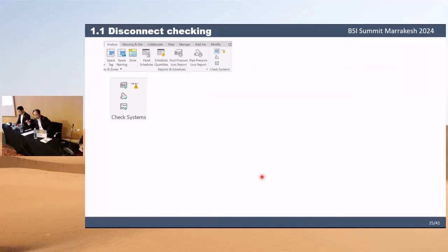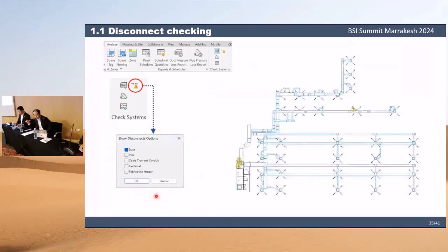On the analysis tab of the Revit ribbon, the show disconnects option tool can be found. You can select the category to analyze. In our study, we select the duct category. For complex systems, it is recommended to assess each category separately. As shown in this figure, there is a disconnect between the diffuser and the duct. Also, there are some disconnects on the third box for supply air. We found the problems came from the family defined by the user. After solving these problems, the duct system can be checked.